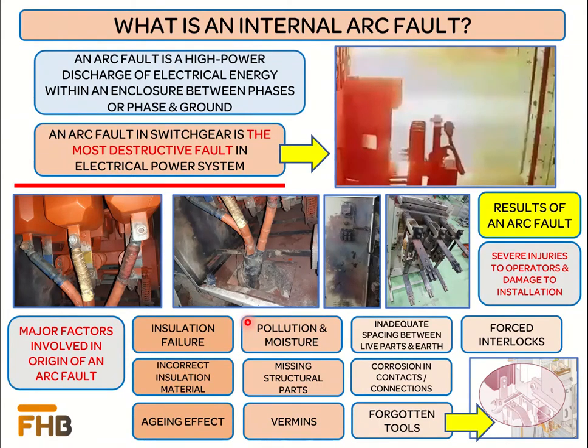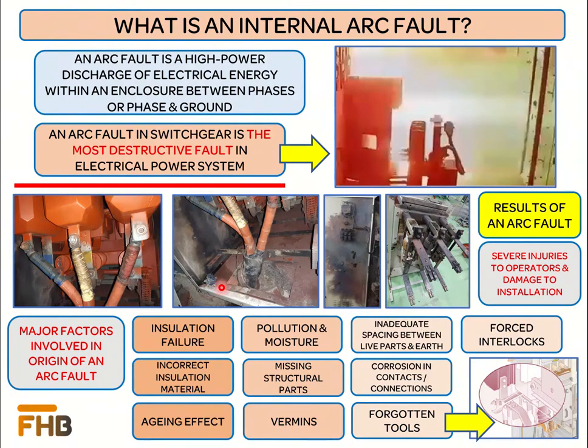The tendency for an arc fault increases if the manufacturer's recommended practices for product installation are not completely followed during the installation and commissioning phase, or if these activities are performed by non-qualified staff. For instance, during the cable termination process, if certain metallic parts such as cable base plates or auxiliary cable duct covers are removed and not reinstalled, or installation is not according to product guidelines, it opens a breach for foreign objects to enter the switchgear and initiate an arc fault. During fastening of cables to copper pads, if the required torque guidelines are not followed, sparking will create heat and may eventually result in the initiation of an arc fault.